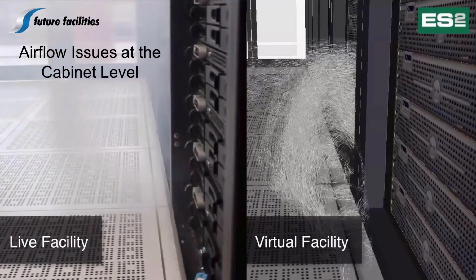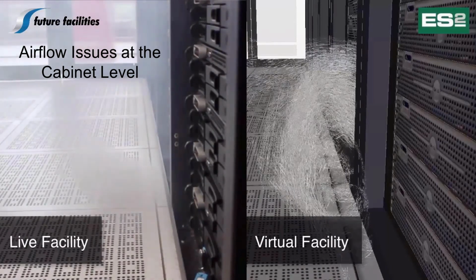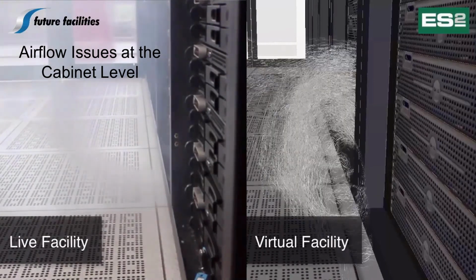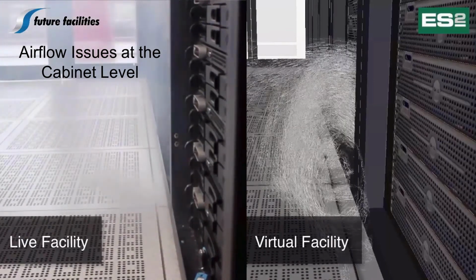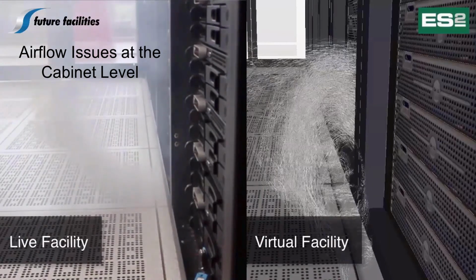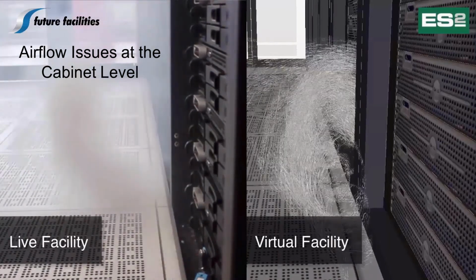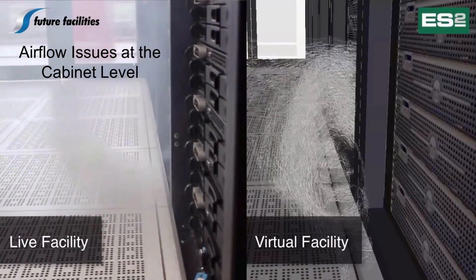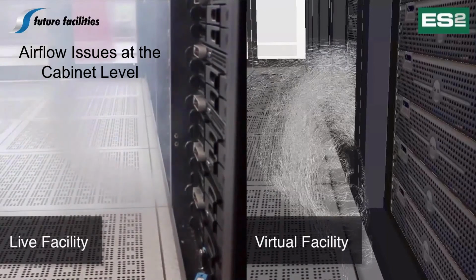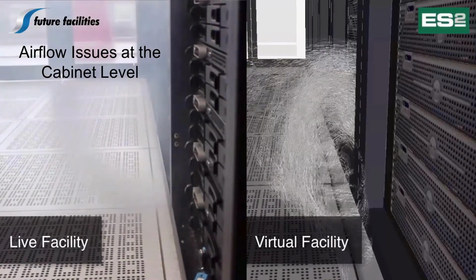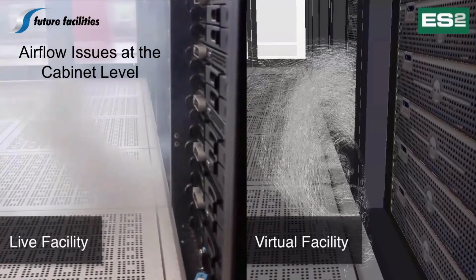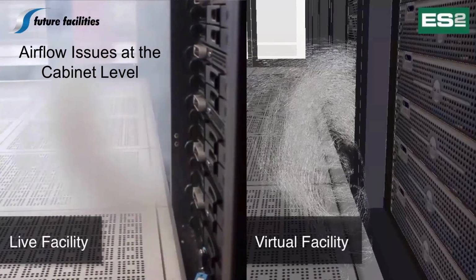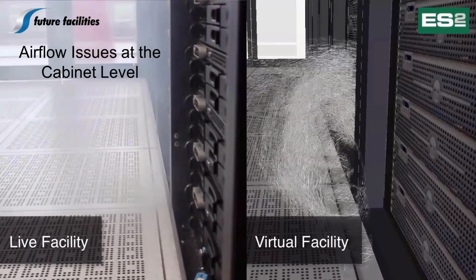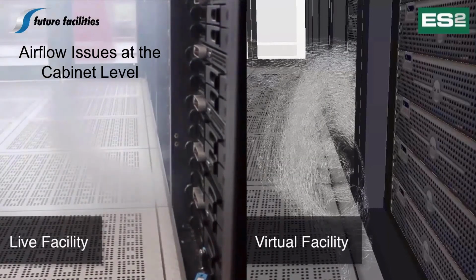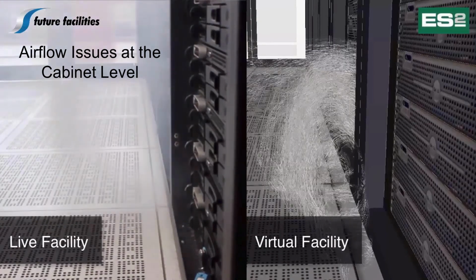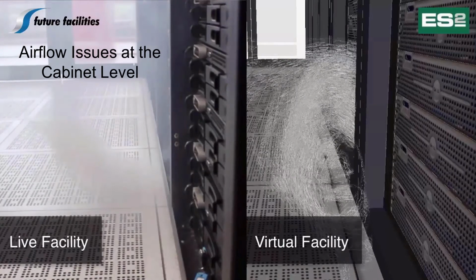So it doesn't have to be a very large space. I've seen just an inch or three-quarters of an inch under cabinets, allowing warm air from the hot aisle to pass underneath the cabinets and cause problems at the bottoms of the cabinets. The engineering simulation is such a valuable way to identify this and to see what the benefits will be once this opening is blocked off.